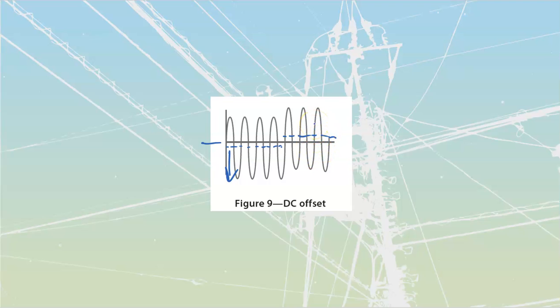Usually it's failure of DC rectification that causes that, where it gets put back onto the line itself. It can cause massive problems with saturation, where I get clipping of my waveforms, because I can't pass the tops of those waveforms all the way through, since transformer magnetic cores get saturated at that point. So I get weird voltages. My voltage gets up to a certain level, my transformer gets ridiculously hot, and I get a weird waveform that's flattened on one side or another.